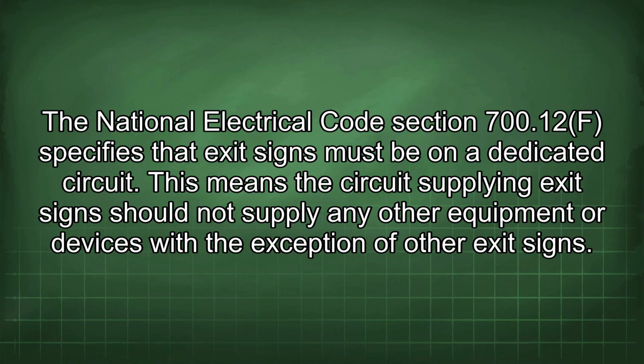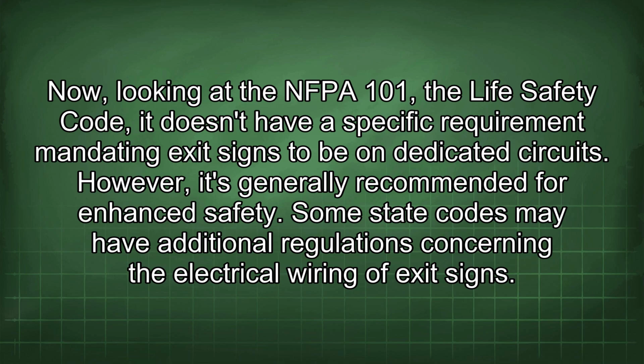The National Electrical Code Section 700.12(F) specifies that exit signs must be on a dedicated circuit. This means the circuit supplying exit signs should not supply any other equipment or devices, with the exception of other exit signs. Now, looking at the NFPA 101, the Life Safety Code, it doesn't have a specific requirement mandating exit signs to be on dedicated circuits. However, it's generally recommended for enhanced safety.